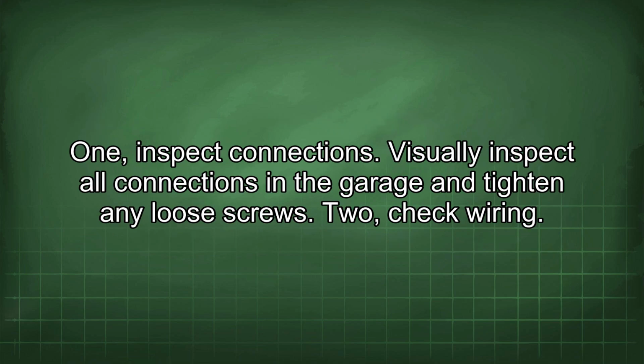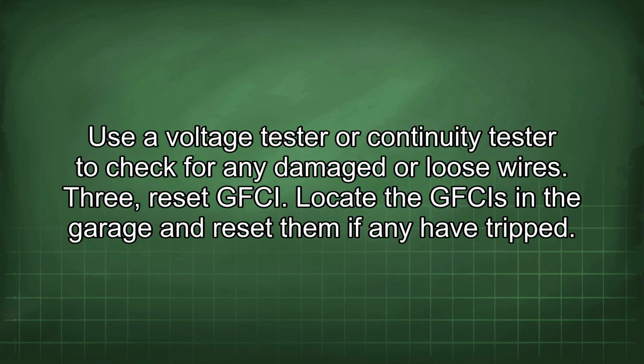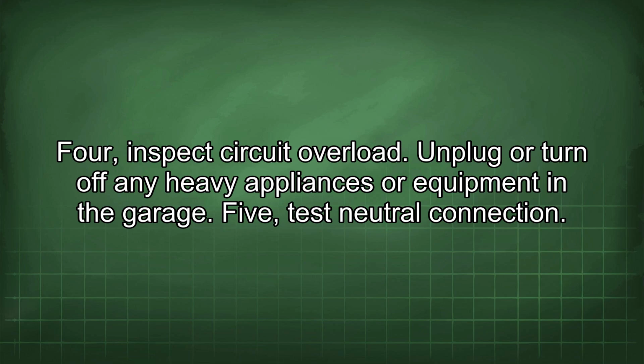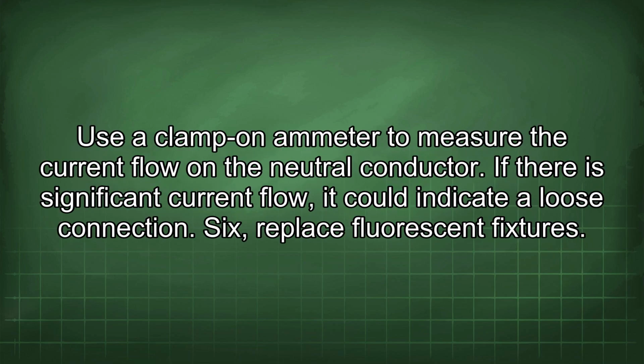1. Inspect connections. Visually inspect all connections in the garage and tighten any loose screws. 2. Check wiring. Use a voltage tester or continuity tester to check for any damaged or loose wires. 3. Reset GFCI. Locate the GFCIs in the garage and reset them if any have tripped. 4. Inspect circuit overload. Unplug or turn off any heavy appliances or equipment in the garage. 5. Test neutral connection. Use a clamp-on ammeter to measure the current flow on the neutral conductor. If there is significant current flow, it could indicate a loose connection.